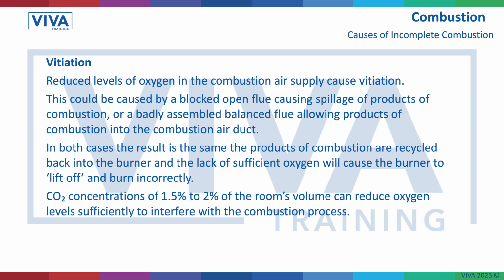It could be that it's a balance flue where you've got an air inlet on the outside of a flue duct, and there's a crack in there, it's become damaged, it's corroded, and you're getting reverse circulation, so it's drawing some of the products back into that appliance, so we're not getting this clean, fresh air that we need. So in both cases, you're going to get the same result. Recycling back off the burner, we're going to get insufficient oxygen, and the CO2 levels are going to alter. Somewhere between 1.5% to 2% of the room volume can reduce that level enough to affect the combustion process.